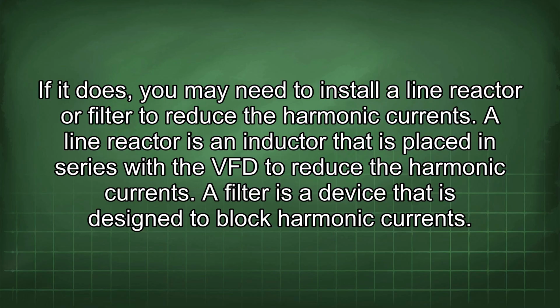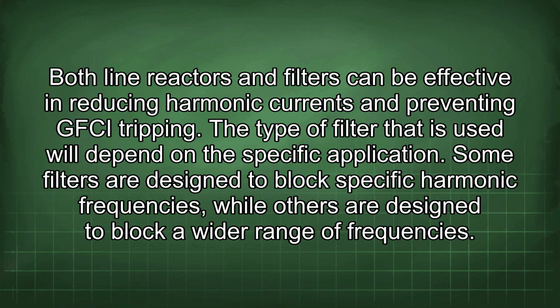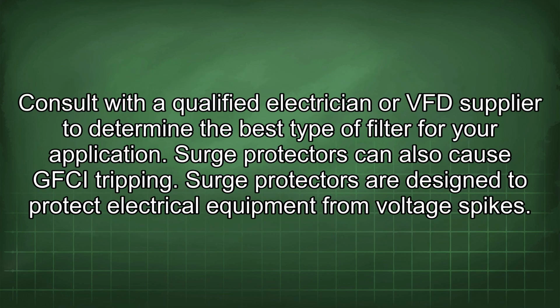A line reactor is an inductor that is placed in series with the VFD to reduce the harmonic currents. A filter is a device that is designed to block harmonic currents. Both line reactors and filters can be effective in reducing harmonic currents and preventing GFCI tripping. The type of filter that is used will depend on the specific application. Some filters are designed to block specific harmonic frequencies, while others are designed to block a wider range of frequencies. Consult with a qualified electrician or VFD supplier to determine the best type of filter for your application.